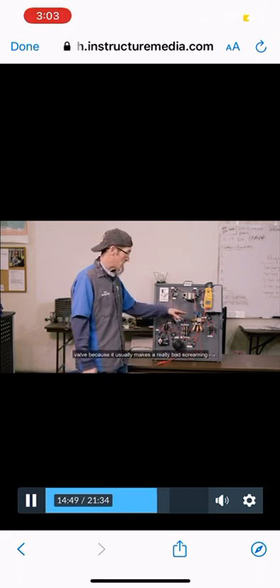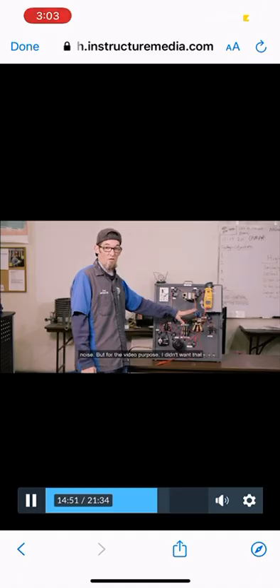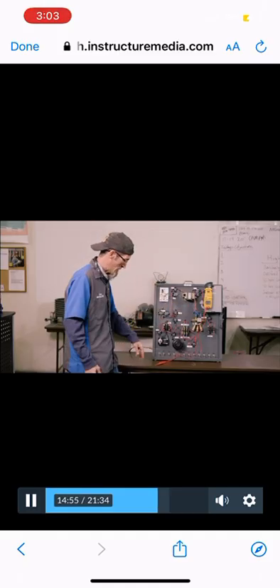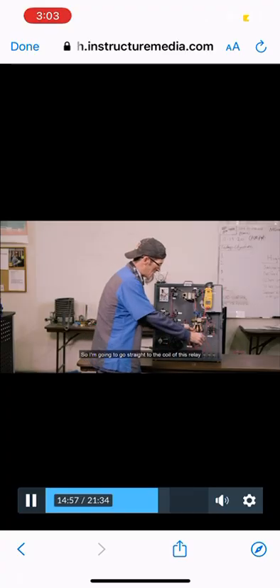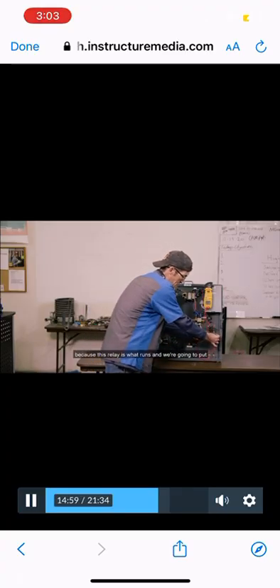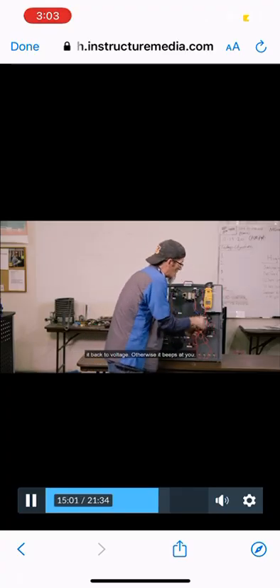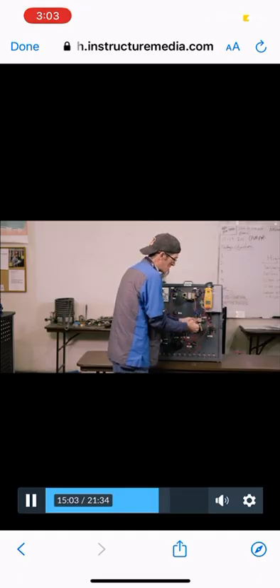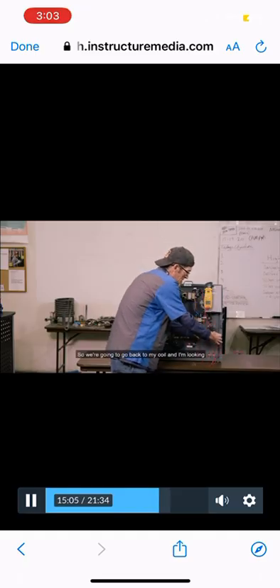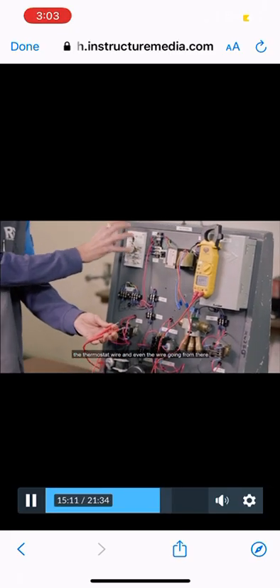Now again, this one I know is my reversing valve because it usually makes a really bad screaming noise, but for the video purpose I didn't want that loud screaming noise going on the whole time. So I'm going to go straight to the coil of this relay because this relay is what runs, and we're going to put it back to voltage, otherwise it beeps at you. Okay, so we're going to go back to my coil and I'm looking for voltage. Now this particular problem, I do have voltage on my coil, which confirms my thermostat, the thermostat wire, and even the wire going from there to there, everything's okay.